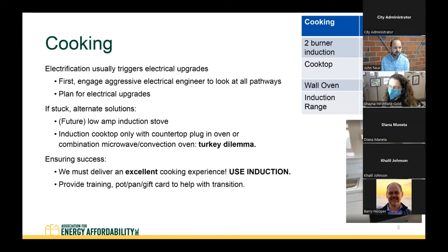We've found that electric and induction ranges are designed for the user to have peak, every burner turned to max, even though folks don't typically cook that way. So we're looking at opportunities to encourage a low amp induction stove to get developed. We've seen some projects, especially in senior buildings, studios, one bedrooms that aren't full family size, move to a cooktop with, say, a built-in microwave oven instead of a full-size range. That also can help reduce the connected load.